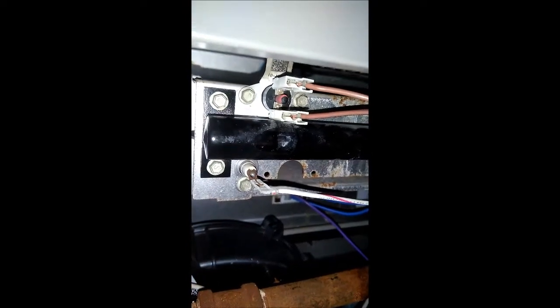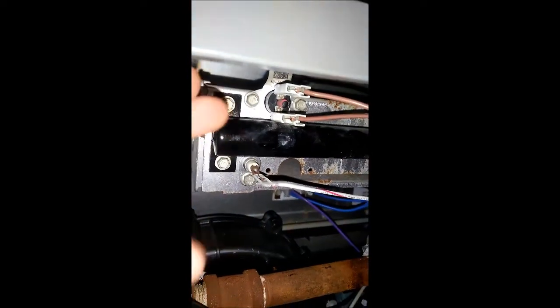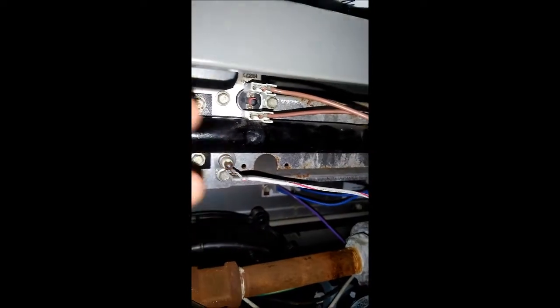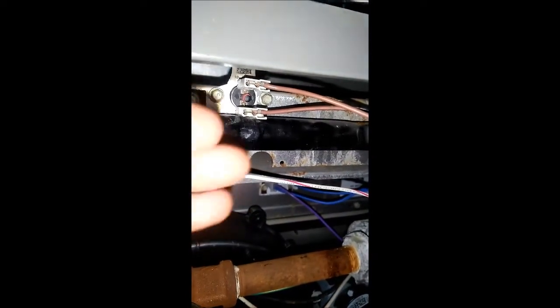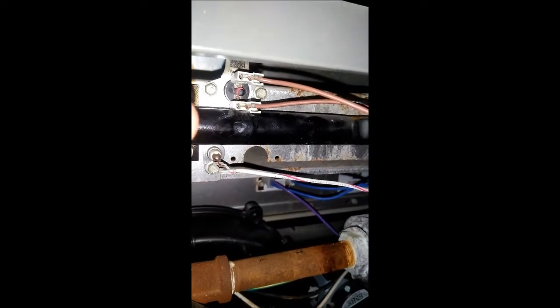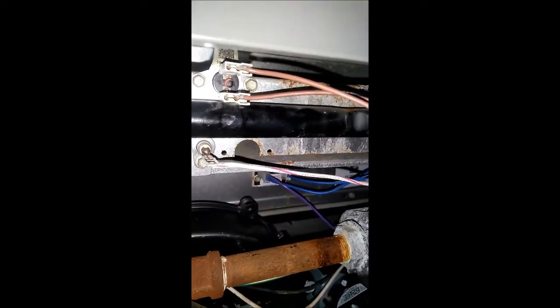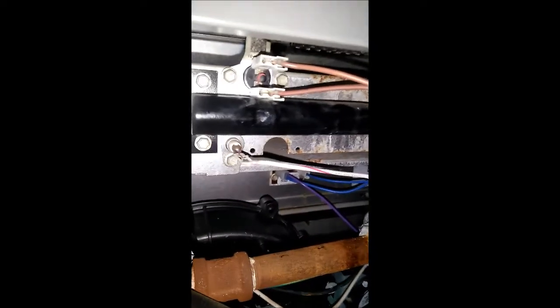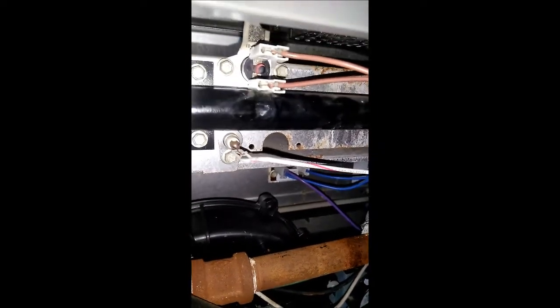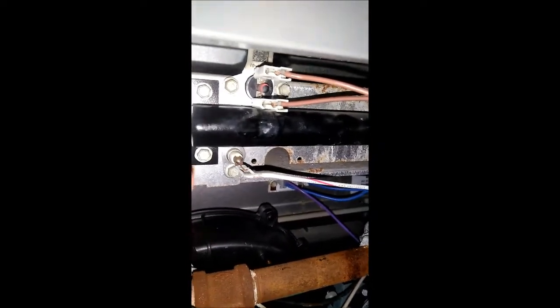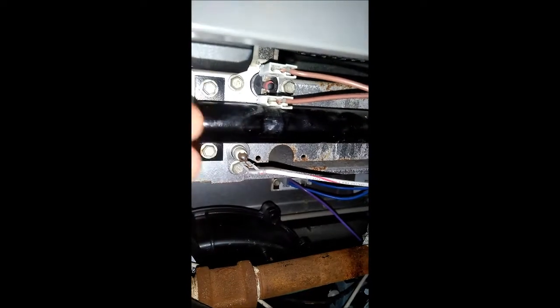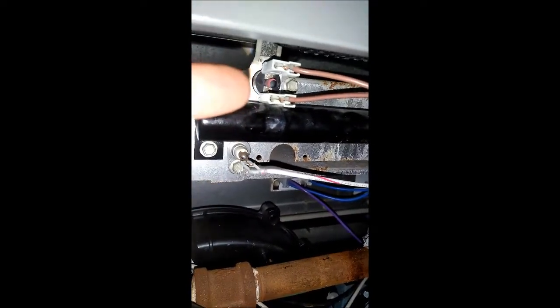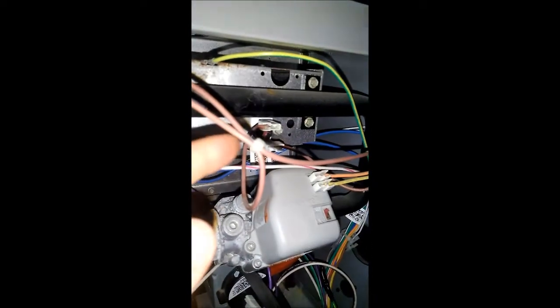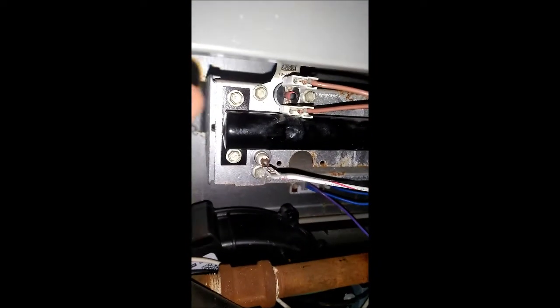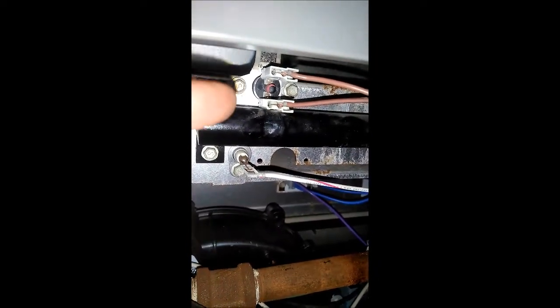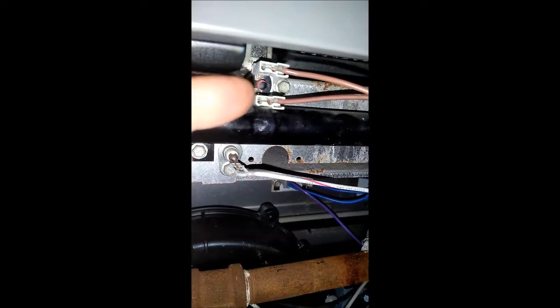It's got a built-in circuit breaker. So what happens is, if for some reason something goes wrong in the furnace and the flames don't go into the heat exchanger, but instead they're backing up into the house, because let's say the heat exchanger is blocked, or there's not enough exhaust vacuum, whatever the reason. If the flame comes back from the burner, from where it's supposed to be, and hits this sensor or that sensor over there, the flame temperature causes some mechanism inside this thing to pop this little switch out.